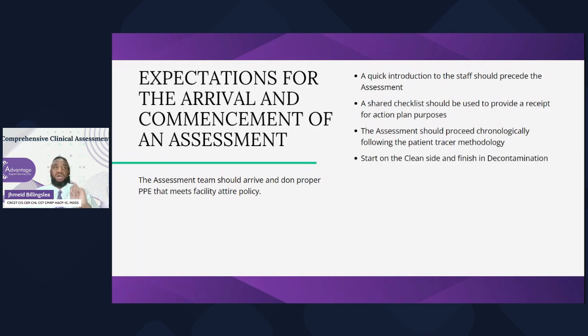You always want to start on the clean side. If someone starts in decon, they're already telling you they don't understand the proper instrument cycle, right? Because you should always end in decon. And yes, we know that if your scrubs are not soiled, you don't necessarily have to change. But also, we know that Cori Ofstead's study showed that aerosolization can go out as far as 7 feet.